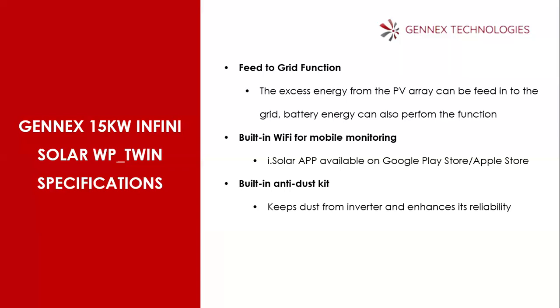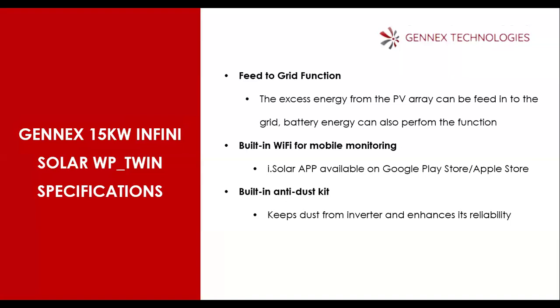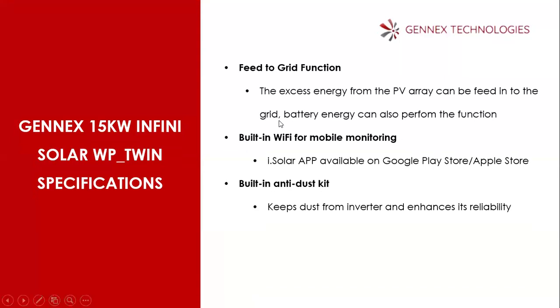Or you can also use it for your own use, to feed back to another inverter to charge another set of batteries, which gives maximum efficiency for other usage. Then as well, you can do that with the battery if the battery is well charged, and you can set your SOC to a particular point. When the battery reaches that level, it can feed to the grid as well, not only the solar panel. You can also use the battery, but it depends on how you want it. You can set it, you can schedule it. When you get to a particular SOC, then it feeds back to the grid or to supply another inverter.